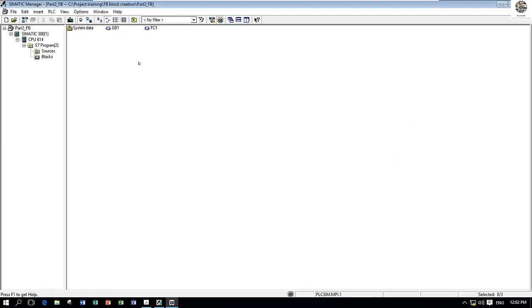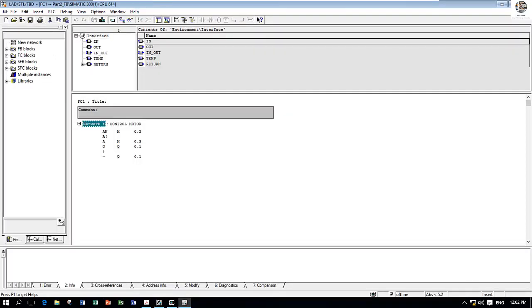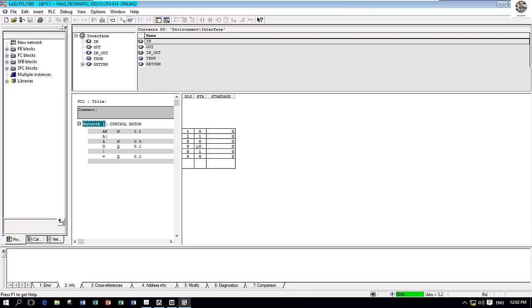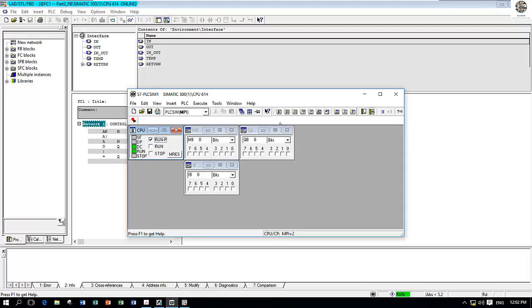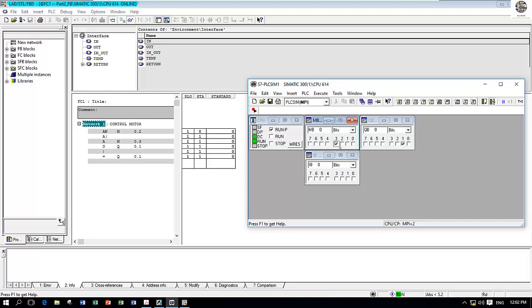To test the function, we can open FC1 and then go online. It shows the status. When I turn on M 0.3, the Q 0.1 is turned on. You see, Q 0.1 is on. When I want to stop, I just press M 0.2, and Q 0.1 is turned off.